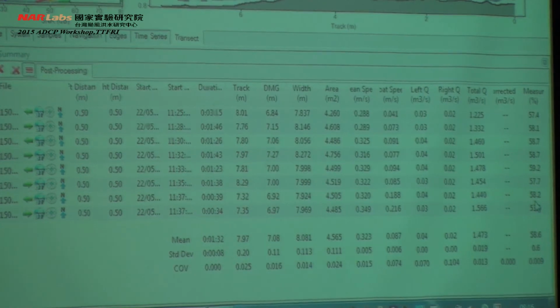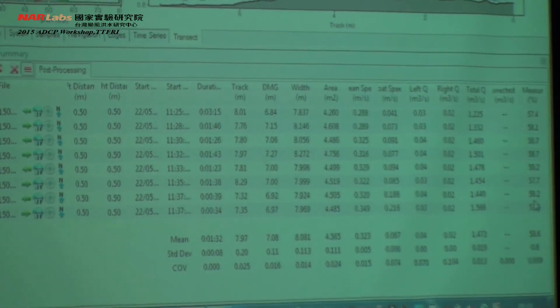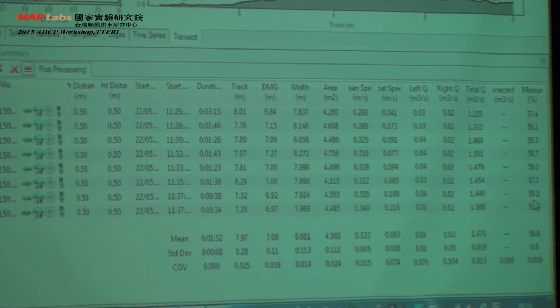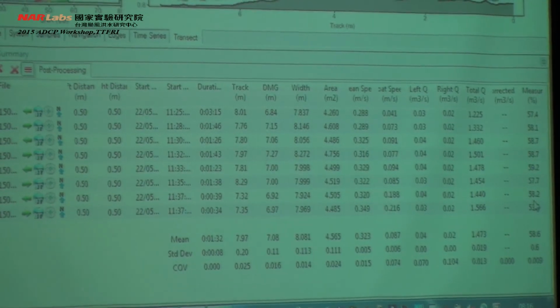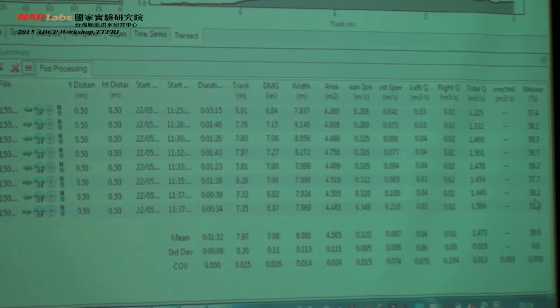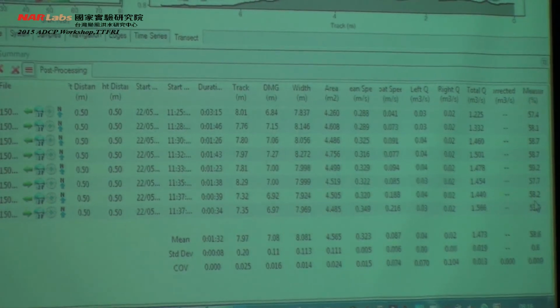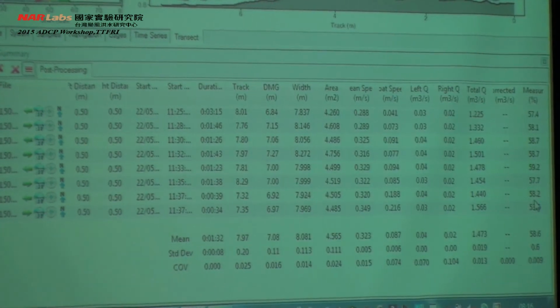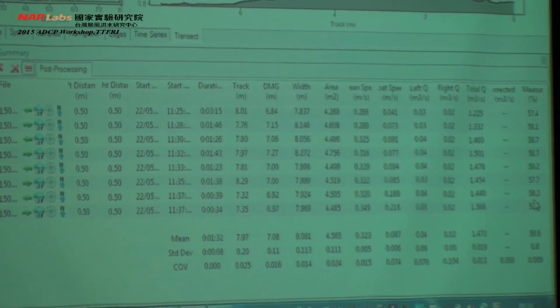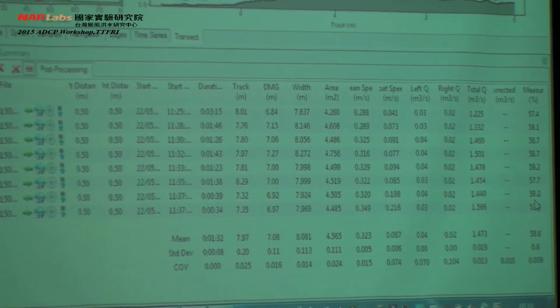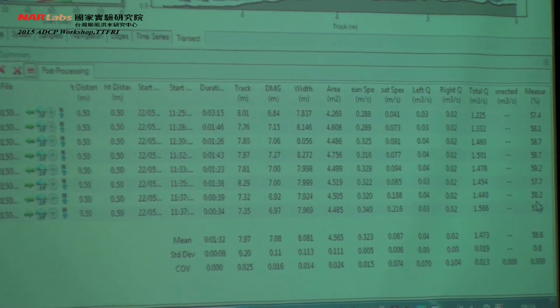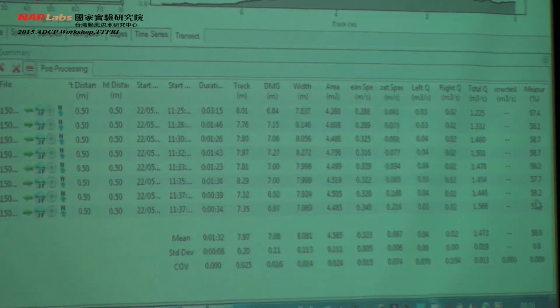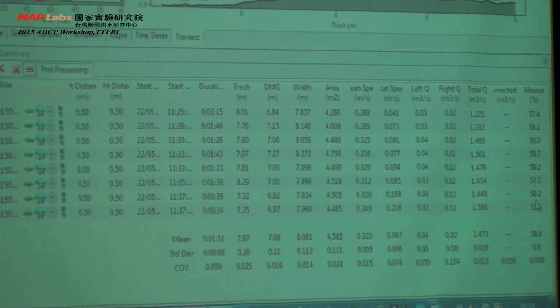Where it's a bit deeper, we can measure more of the velocity. But if it's the only site that you can possibly go to, then just spend a bit more time at the site, ensuring that you do as good a measurement as possible, and then you can say with a lot more confidence, actually no, even though we've only got 40%, 35%. When you look at all the rest of it, your total Q, the deviation, the variation between the measurements and everything else that gives you confidence, you say, no, I can accept this.